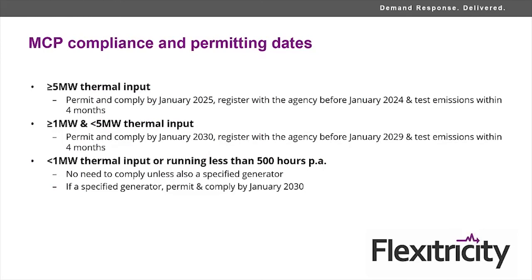For the 2 megawatt electrical down, the 5 megawatt thermal input down, they have another 5 years to do that. But again, registering and testing emissions happens 1 year prior to the date by which it has to be compliant. And if it's less than 1 megawatt thermal input, or if it's running less than 500 hours per annum, well, it's not an MCP. So it doesn't have to comply with any of this legislation unless it's also a specified generator.